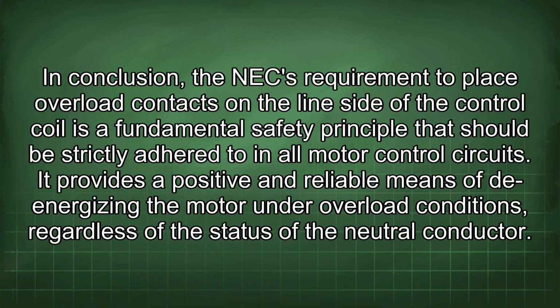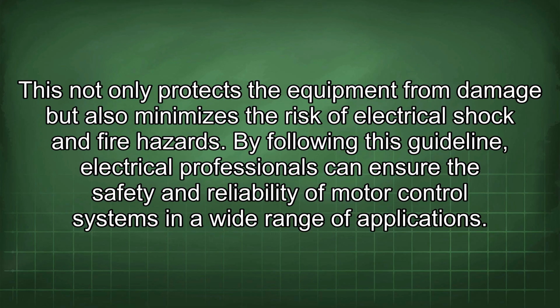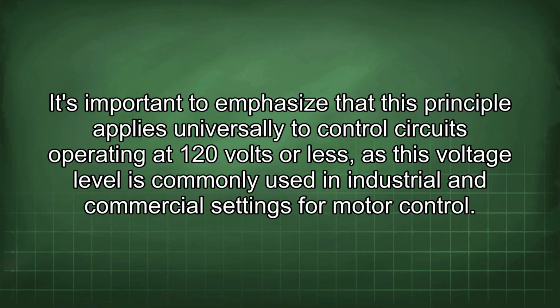In conclusion, the NEC requirement to place overload contacts on the line side of the control coil is a fundamental safety principle that should be strictly adhered to in all motor control circuits. It provides a positive and reliable means of de-energizing the motor under overload conditions regardless of the status of the neutral conductor. This not only protects the equipment from damage but also minimizes the risk of electrical shock and fire hazards. By following this guideline, electrical professionals can ensure the safety and reliability of motor control systems in a wide range of applications. It's important to emphasize that this principle applies universally to control circuits operating at 120 volts or less, as this voltage level is commonly used in industrial and commercial settings for motor control.